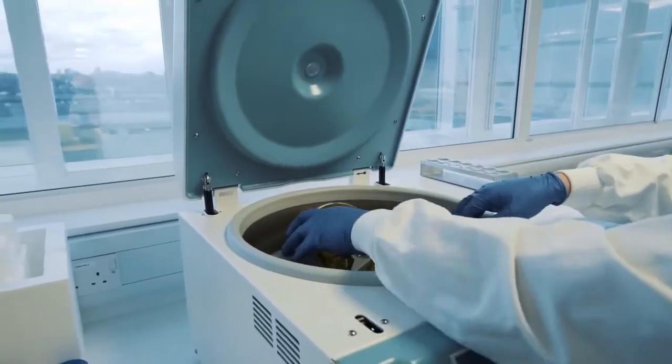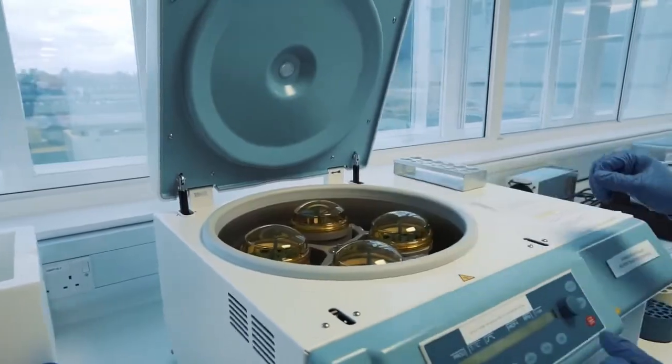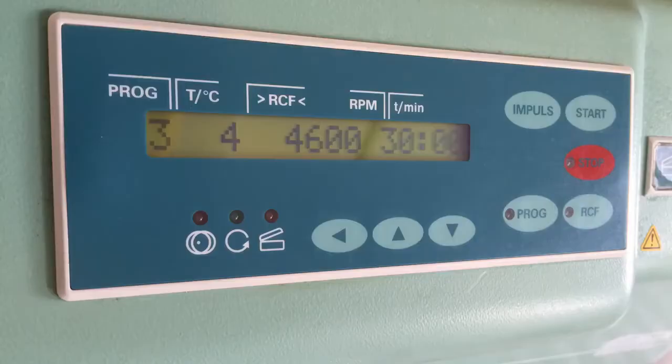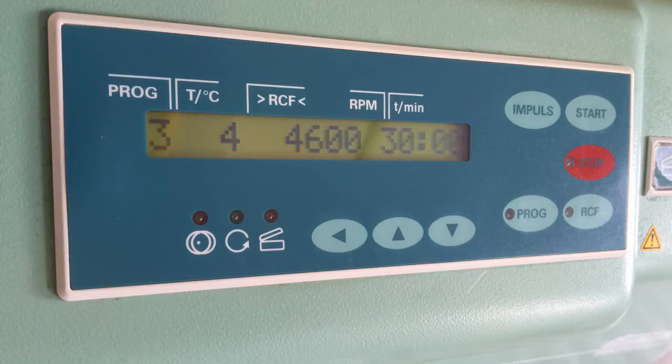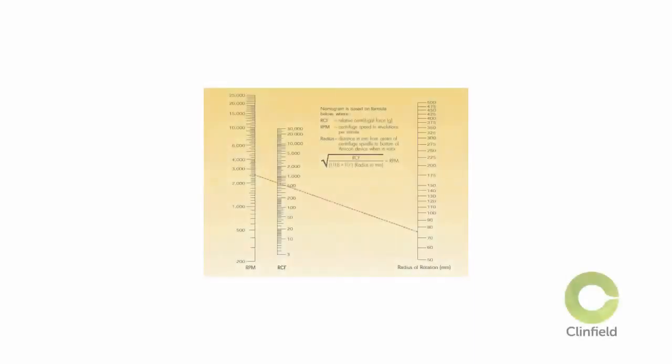You're now ready to set the centrifuge controls to start. Some protocols refer to spinning samples at a specific speed or RPM, which stands for revolutions per minute. While some refer to spinning at a specific G-force or RCF, which stands for relative centrifugal force. This is measured in a number times the force of gravity. For example, 1000 G is 1000 times the force of gravity.